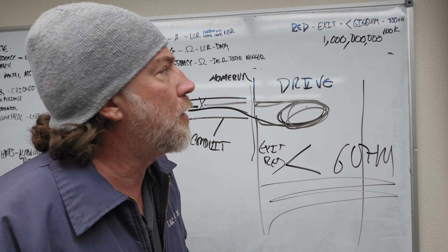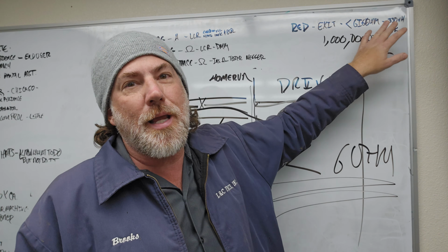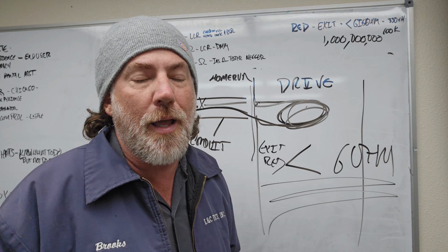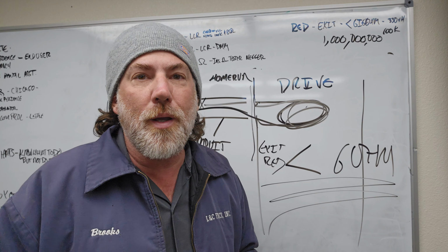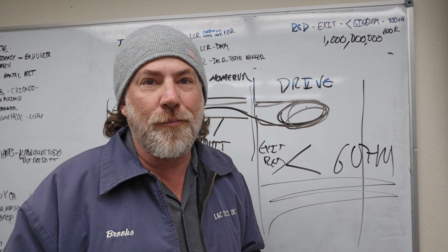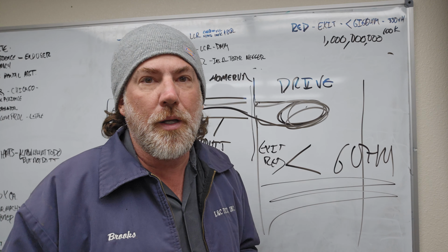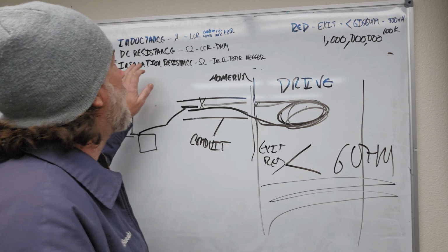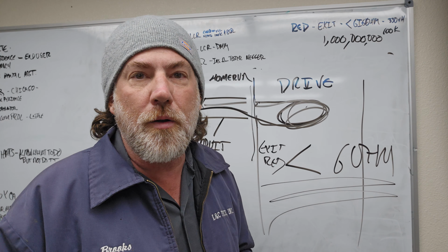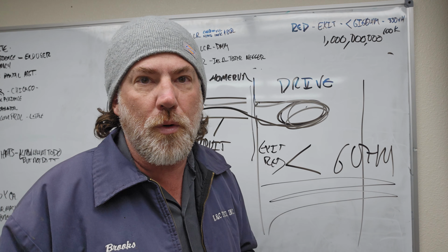On top of that, when I do a new install, look at what I've documented: the color of the loop wire, the function of the loop, its resistance, and what its inductance actually is. And if you're just going in there and saying, well, everything worked from the beginning, I have no documentation to prove what it was. And you go in and you go, well, the loop's 30 million ohms. So that's right there on the borderline. No, if it's been 30 million ohms for 10 years, then no, it's actually not on the borderline. It's been that and worked for 10 years. And until you get a good picture of the DC resistance and inductance, it's going to be really hard for you to be able to stand in front of 100 people or 50 people like I did on Friday and convince them that you're the expert.